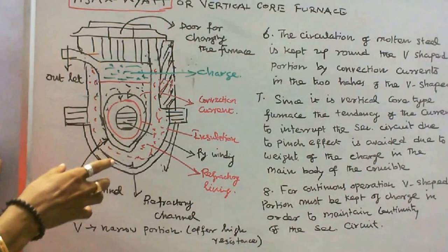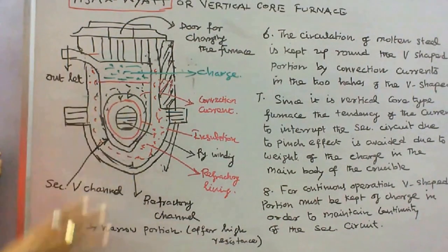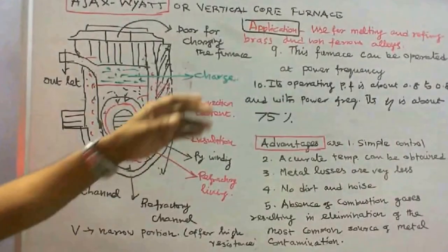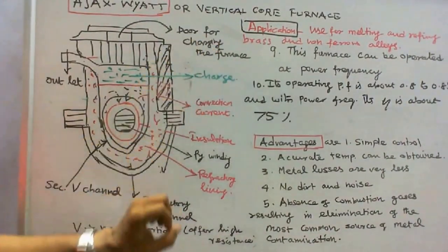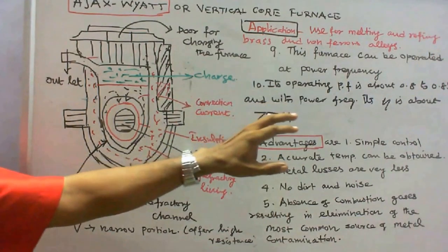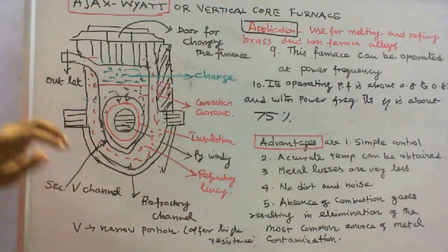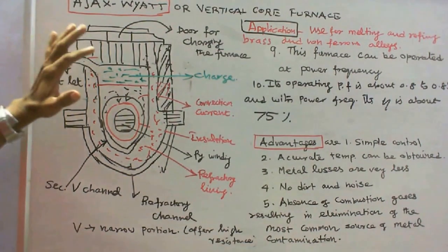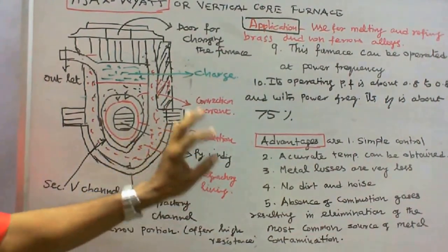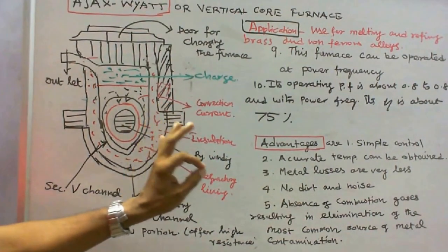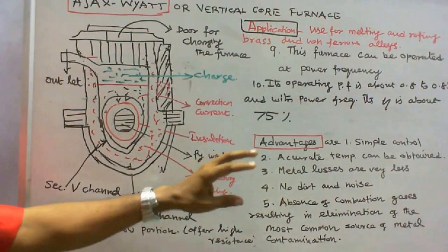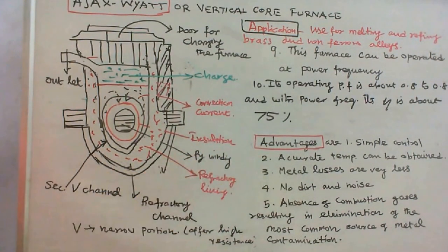For continuous operation, the V-shaped portion must be kept full of charge in order to maintain continuity of the secondary circuit. The furnace can be operated at power frequency, and its operating power factor is about 0.8 to 0.85. With power frequency, its efficiency is about 75%. The advantages of Ajax-Wyatt Furnace are: 1. Simple control; 2. Accurate temperature can be obtained; 3. Metal losses are very less; 4. No dirt and noise; 5. Absence of combustion gases, resulting in elimination of the most common source of metal contamination.